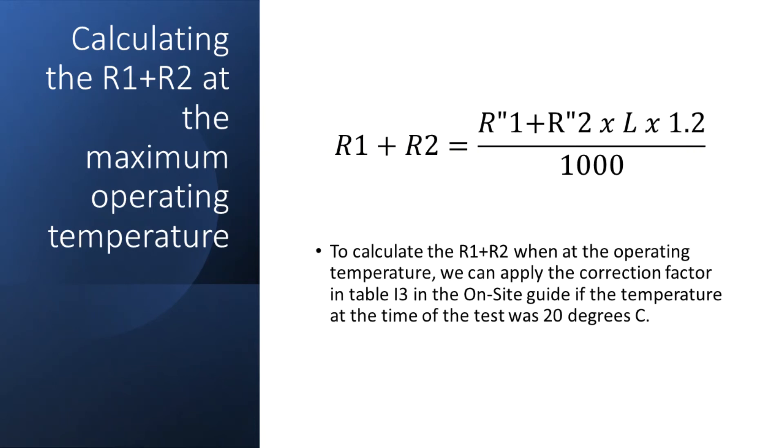So for the same reason that we subtract 20 percent from the maximum permitted ZS, when calculating R1 plus R2 we can use the correction factor to add that 20 percent to allow for the increase in the temperature of the circuit when it's under load.